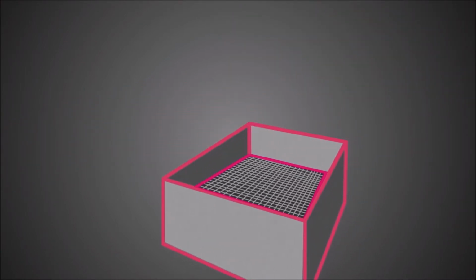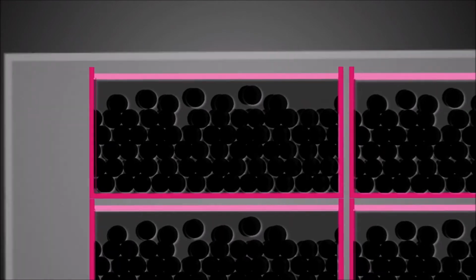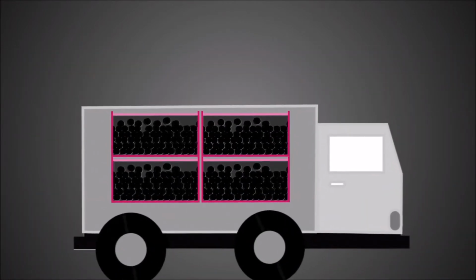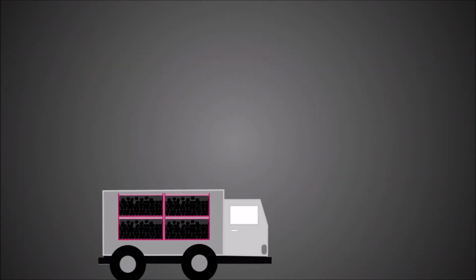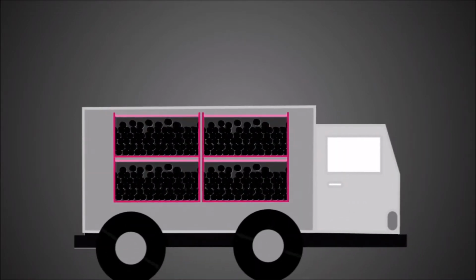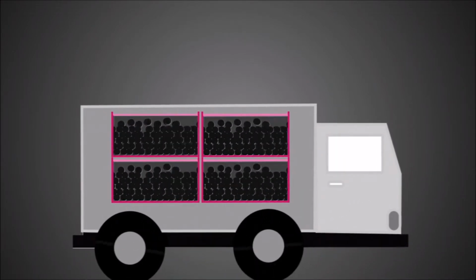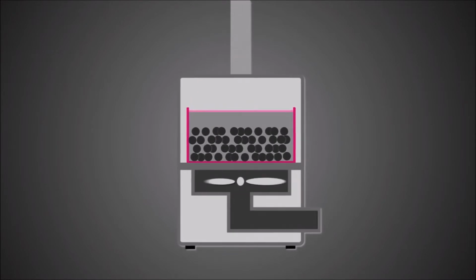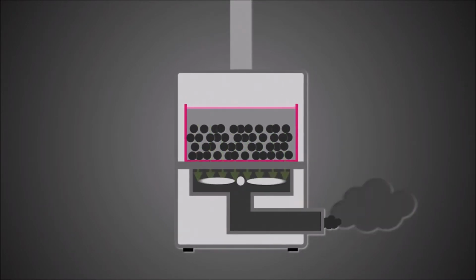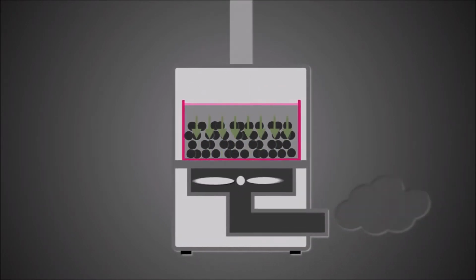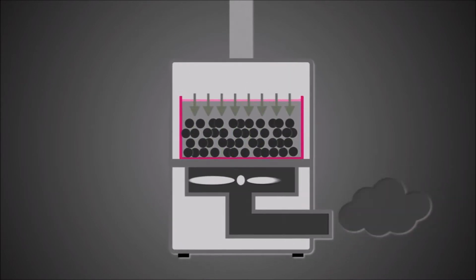If the carbon is loose, the granules settle. This can happen initially during transportation, where the carbon granules compact. An airspace is then created between the carbon layer and the top layer, where a considerable amount of carbon dust is generated. When the filter is first used, the initial problem comes from the carbon dust, which is blown through the exhaust, polluting the air within the environment.